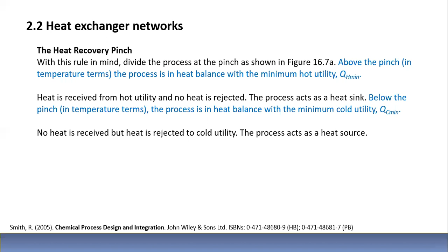So here we see a delta T minimum of 10 degrees Celsius. Saying how heat transfer from above the pinch to below the pinch is possible. This is the pinch right there. The pinch identifies the place where we have a minimum delta T. So above the pinch can exchange heat with a point below the pinch. But what cannot be possible is to go from below the pinch and to exchange heat to a point above the pinch. So you see here, we're going from 185 to 95.